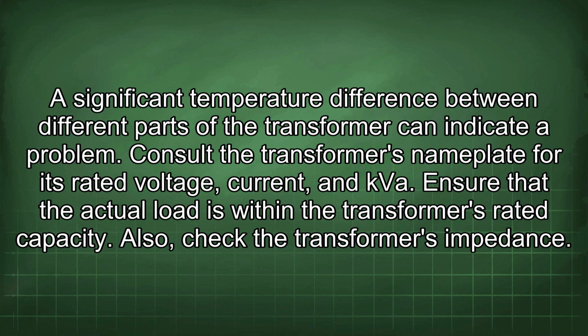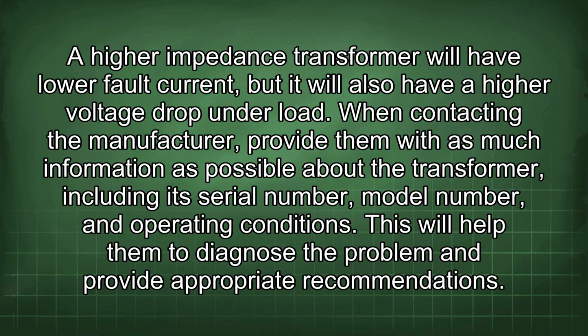Consult the transformer's nameplate for its rated voltage, current, and kVA. Ensure that the actual load is within the transformer's rated capacity. Also, check the transformer's impedance. A higher impedance transformer will have lower fault current, but it will also have a higher voltage drop under load.